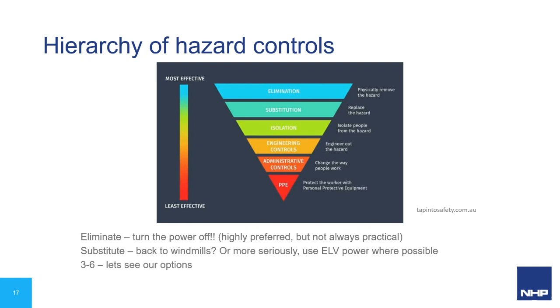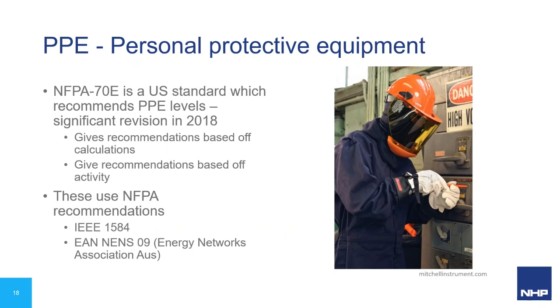And 3 to 6, let's see what our options are. Let's start at the bottom. Let's talk about PPE a little bit. Personal protective equipment. When we're working with this sort of stuff, we're talking about pretty serious equipment. There's actually a reluctance in a lot of documents to specifically say exactly what equipment to use. Usually the wording is something like use appropriate PPE, which doesn't really help you too much. But there is one standard that brings that through, which is the NFPA 70E, which is a US standard, which goes in and gives recommended PPE levels.